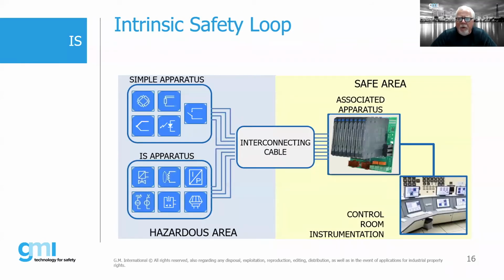So there's, again, that loop we talk about. And actually, when we talk about all the protection concepts, when we teach Compex or the IECEx CoPC program, one of the things that surprises people is that of all the protection concepts, IS is a true system concept. As I mentioned, we have to take into account the simple apparatus or the IS apparatus, our interconnecting cable, our associated apparatus, and our control room that's providing the power into the system. All the other protection concepts that we talk about, including Ex d, Ex p, Ex e, are basically standalone protection devices or concepts. And generally speaking, they're all really mechanical protection concepts, where intrinsic safety is a true electrical concept.